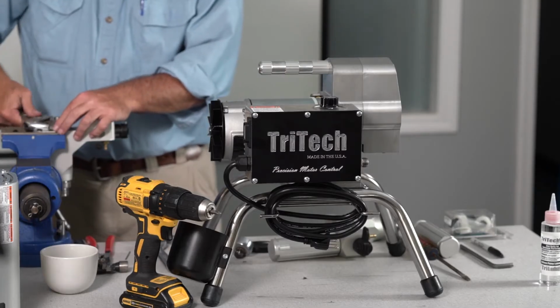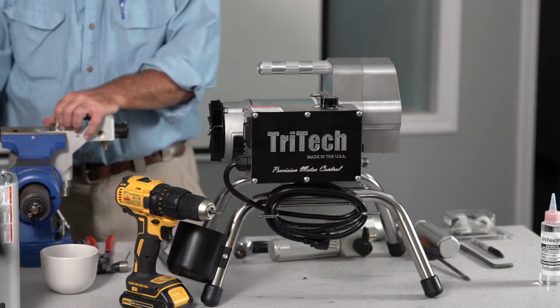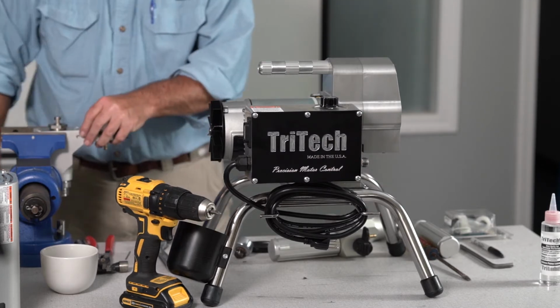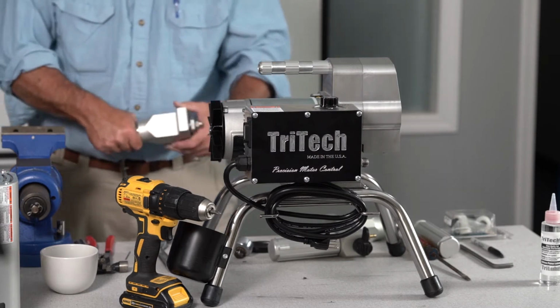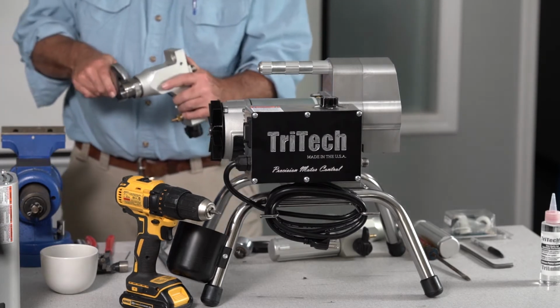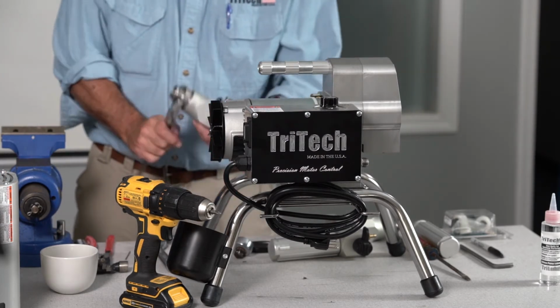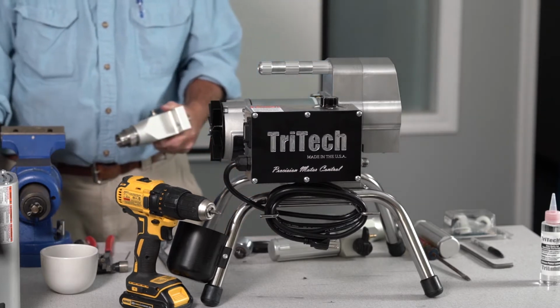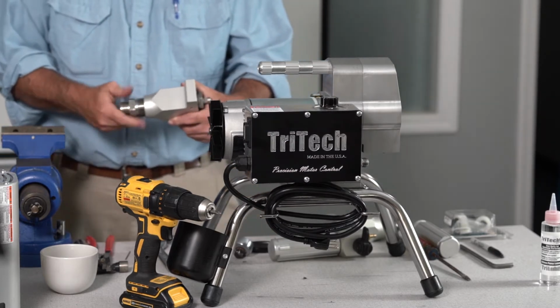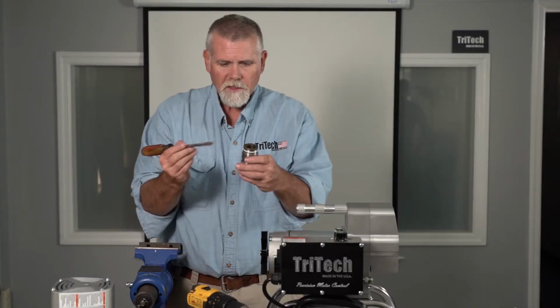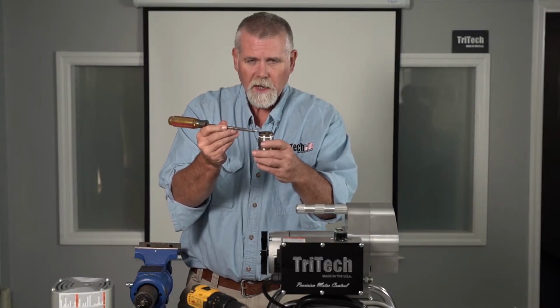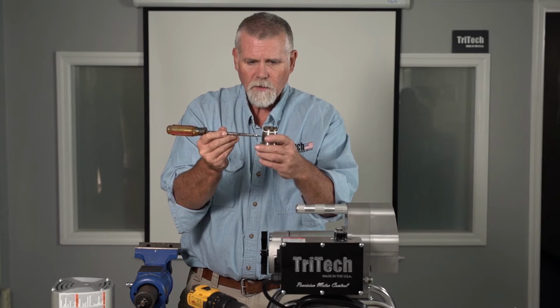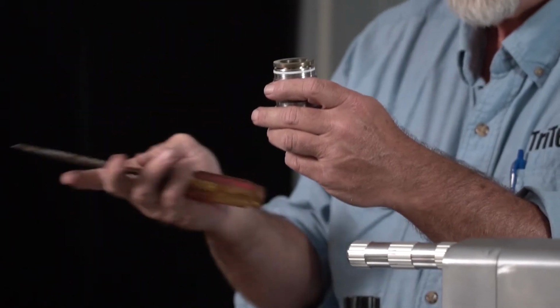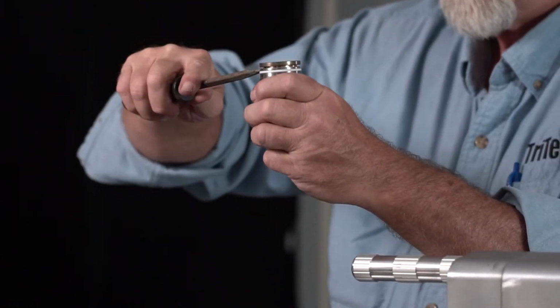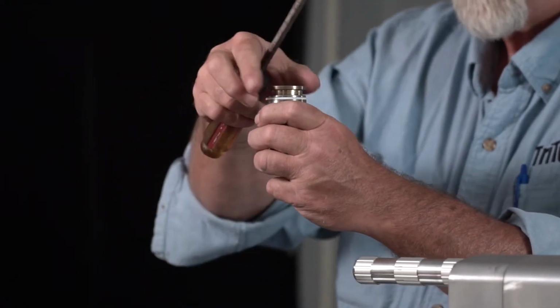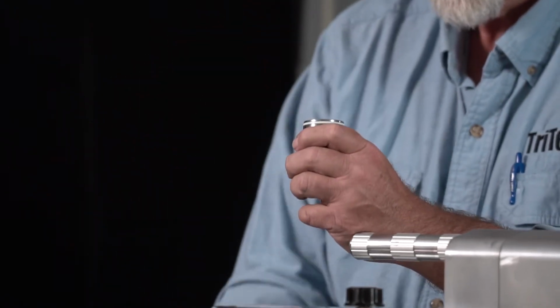Then we're going to loosen our upper packing retainer. We're not going to take it off just yet. And then we're going to take off our foot valve. This slot between your inlet valve retainer and your foot valve housing is there on purpose. The reason for the slot is that you can put a straight blade screwdriver in there and pry that up to make it easier to remove.